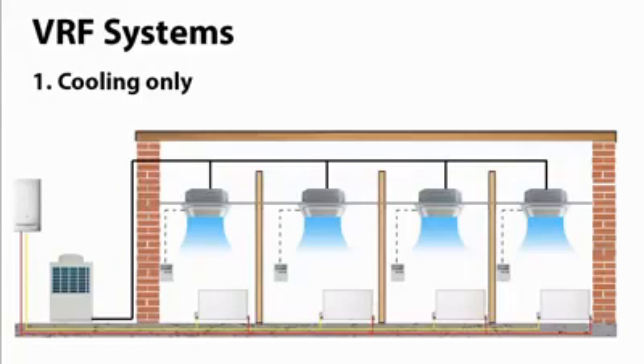Although this might not be the best approach because you're probably going to get some conflict between the two if the correct controls are not set up. And what you don't want to occur is that the heat being generated by the radiator to heat the room is being absorbed by the ceiling cassette, which is providing cooling. So the two are fighting each other to try and maintain the correct temperature in the room. This would obviously waste a lot of energy, so this might not be the best approach.